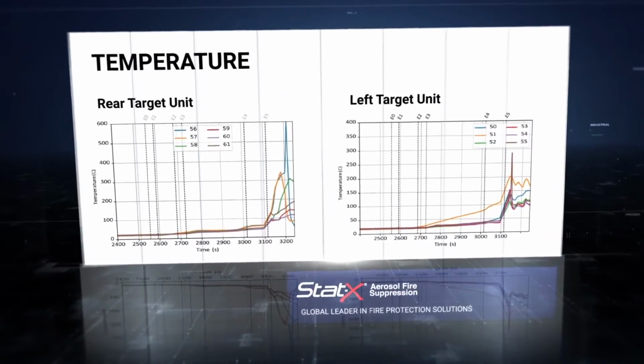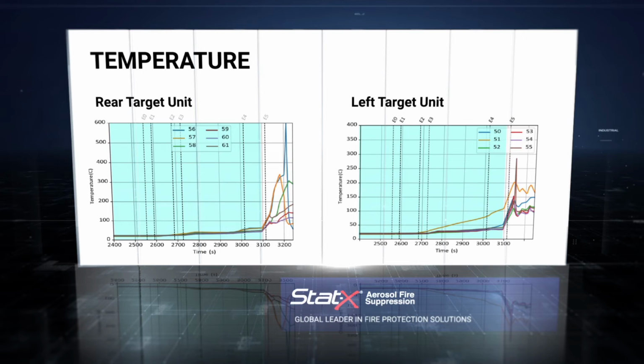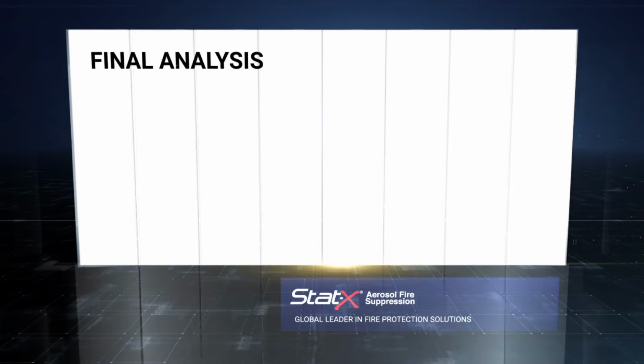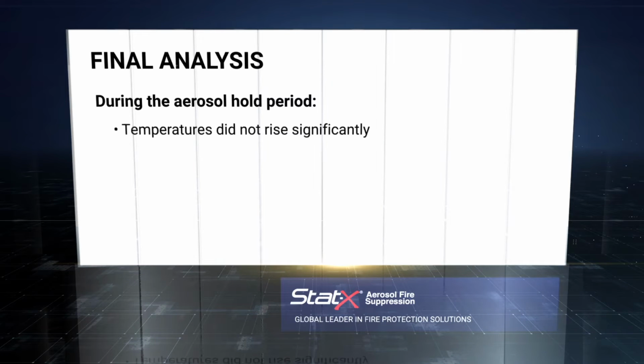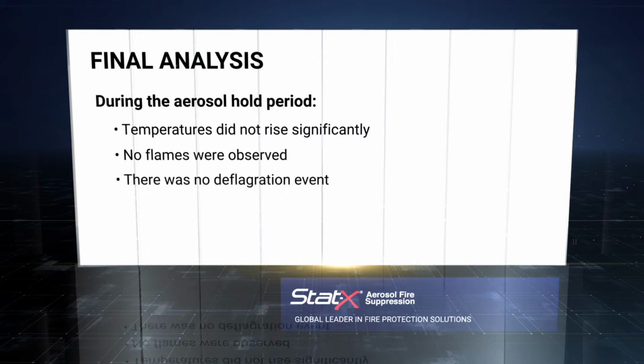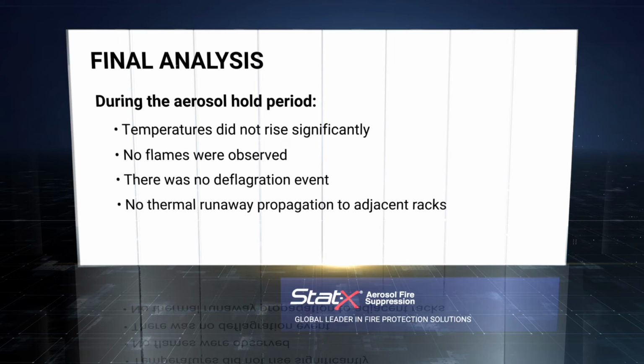Tracking the temperature of the rear and left target units, it's clear the temperature did not rise once the aerosol was released. Note that the only spike in temperature came as the enclosure was ventilated and oxygen entered the environment. This is to be expected when oxygen is added and aerosol density is quickly reduced. Final analysis revealed that during the aerosol hold period, temperatures did not rise significantly. No flames were observed. There was no deflagration event, and there was no thermal runaway propagation to adjacent racks.